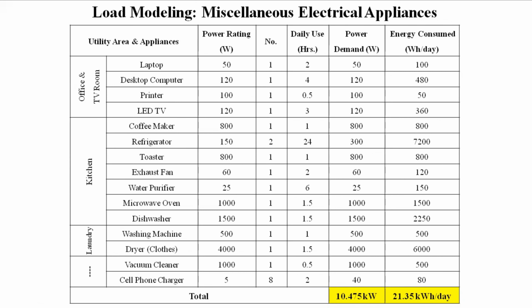And if I just sum up the energy consumed by all these MELs, it comes around 21.35 kWh per day, and most of it will be consumed by dryer and refrigerator, which will be more than 60%, and the maximum connected load on a particular day would not exceed 10.475 kW if all these are running simultaneously. Now, Santosh will go over lighting, HVAC, water heating, and farming load.